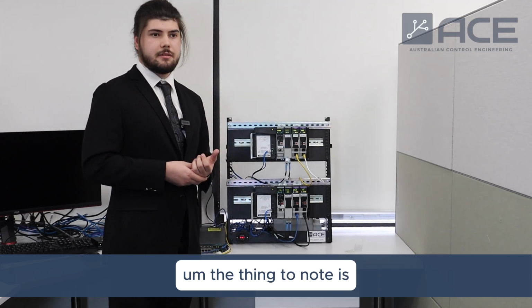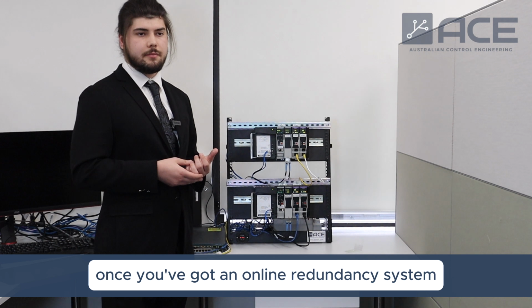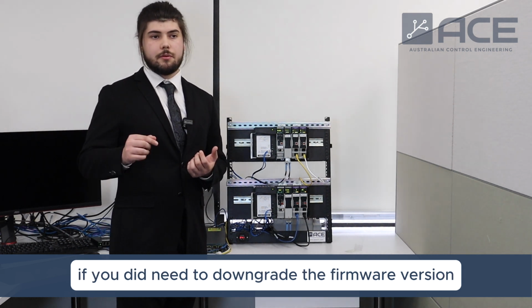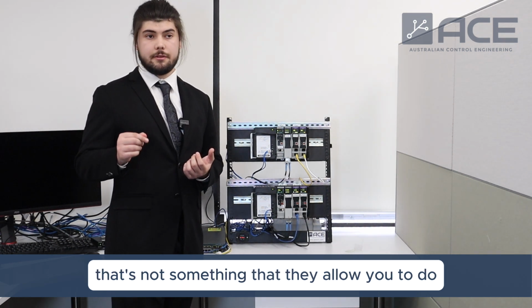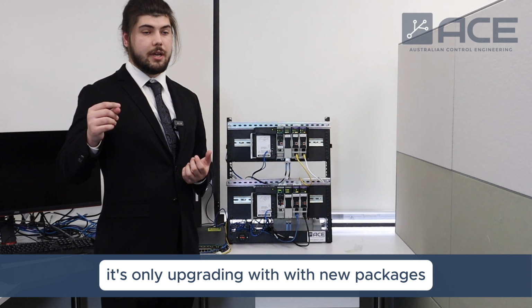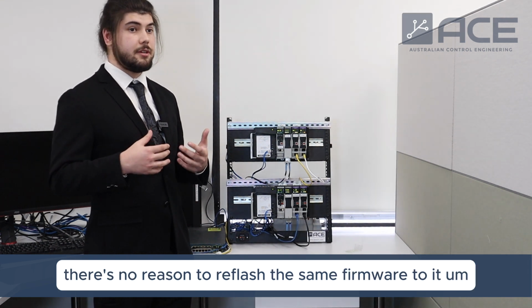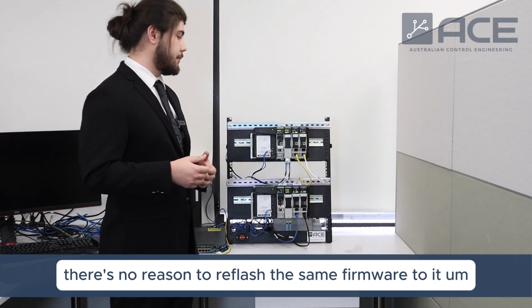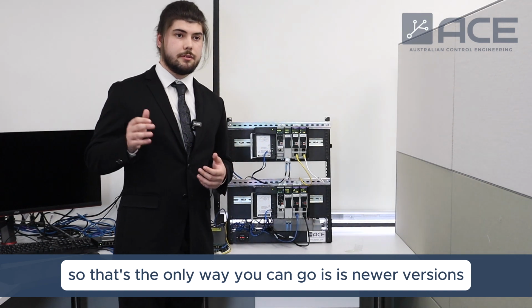The thing to note is, once you've got an online redundancy system, if you did need to downgrade the firmware version, that's not something that they allow you to do. It's only upgrading with new packages, and obviously there's no reason to reflash the same firmware to it. So the only way you can go is newer versions.